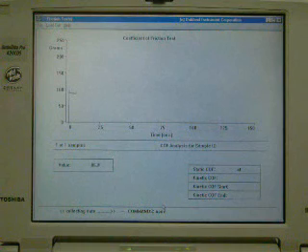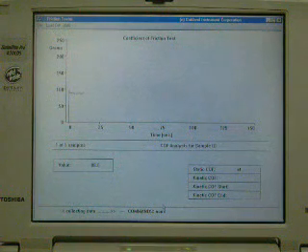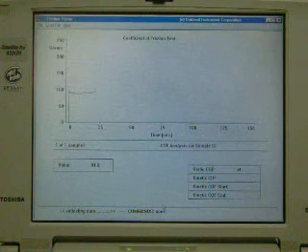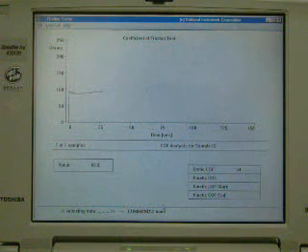If following ASTM or other standards, you are typically required to record product or specimen description, sample conditioning procedure followed, instrument configuration and setup, testing technique used, specimen thickness, surfaces tested, principal directions tested, approximate age of sample after manufacture, date and operator name, average static and kinetic coefficients of friction, together with the standard deviation and number of specimens tested for each COF.